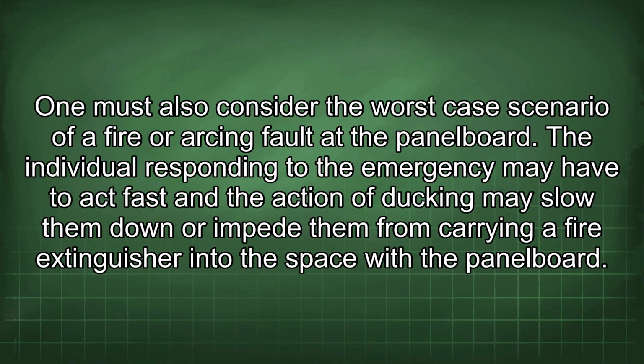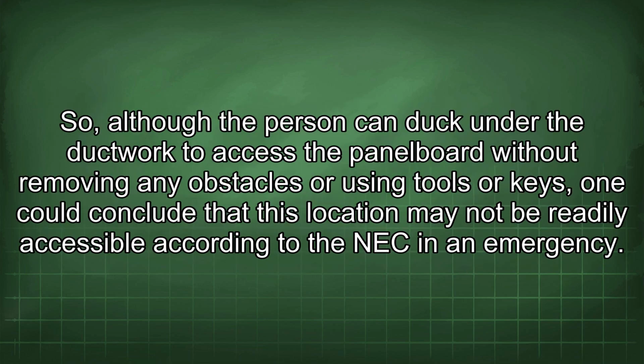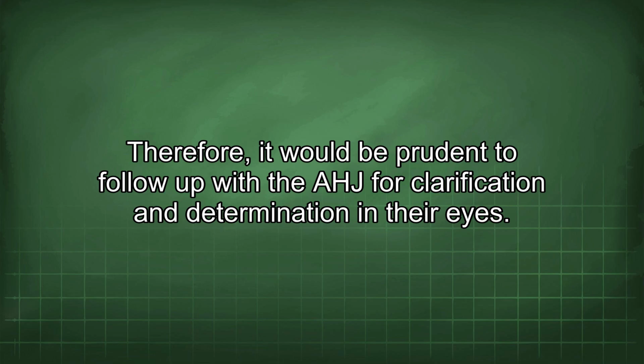One must also consider the worst-case scenario of a fire or arcing fault at the panel board. The individual responding to the emergency may have to act fast, and the action of ducking may slow them down or impede them from carrying a fire extinguisher into the space with the panel board. So, although the person can duck under the ductwork to access the panel board without removing any obstacles or using tools or keys, one could conclude that this location may not be readily accessible according to the NEC in an emergency. Therefore, it would be prudent to follow up with the AHJ for clarification and determination in their eyes.